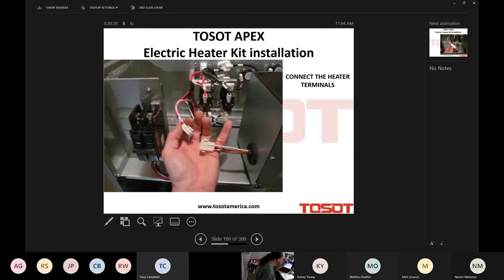Now, remember where we started, people? Remember where we started? I told you that if you use the electric strip heater, you're going to power it, and you're not going to power L1 and L2 of the indoor unit. Maybe I didn't tell you that. Sorry about that. I should have. You're going to bring your source power to the breaker. You are no longer going to bring the source power to L1, L2 of the indoor unit. Once again, you'll see what I mean.